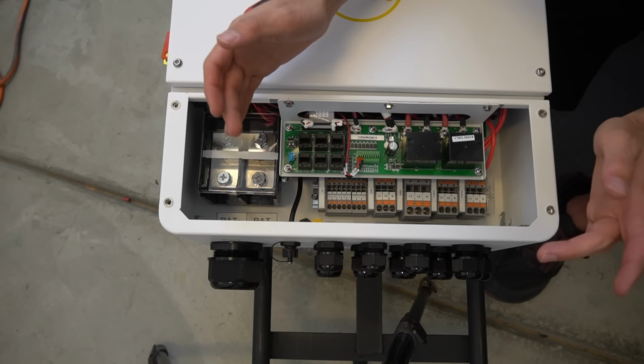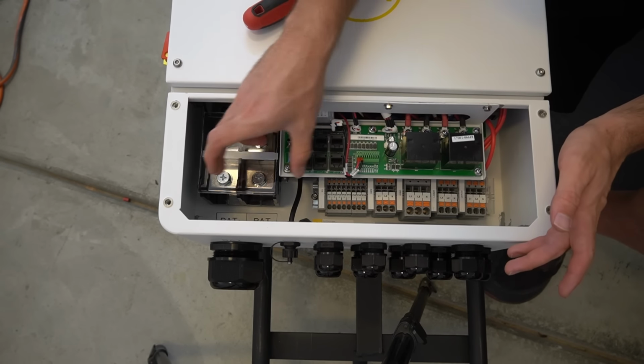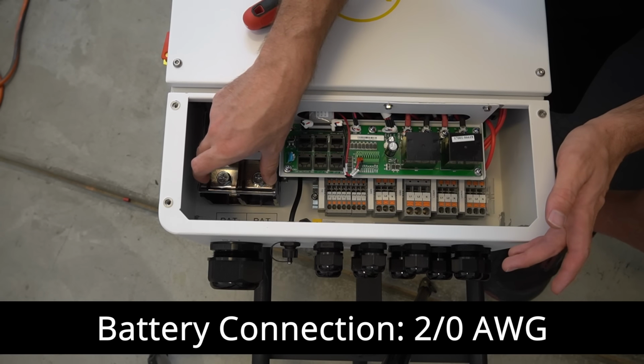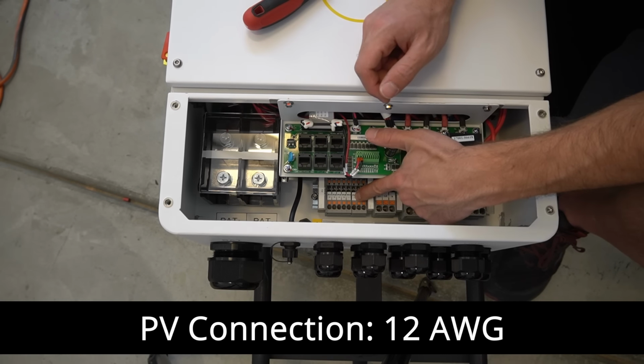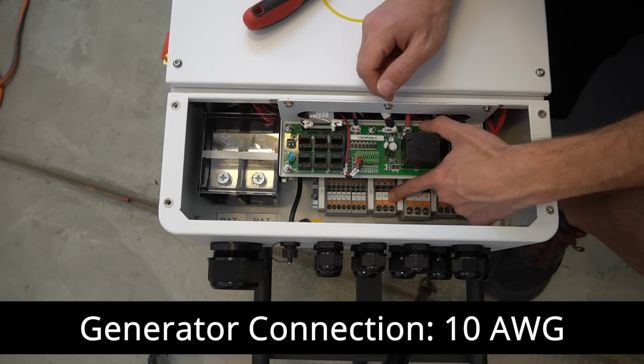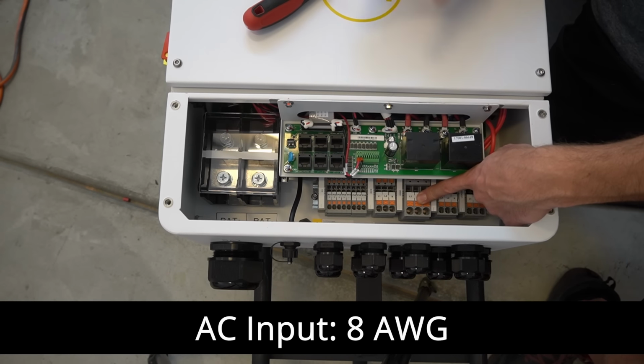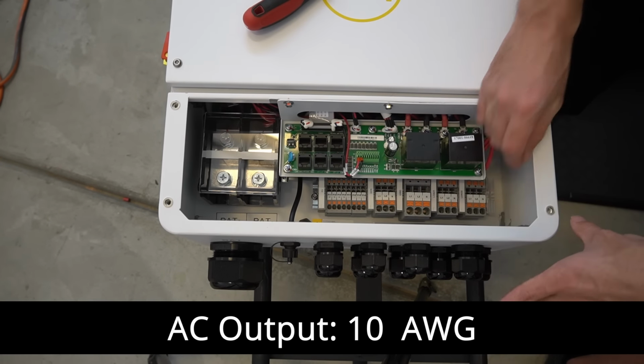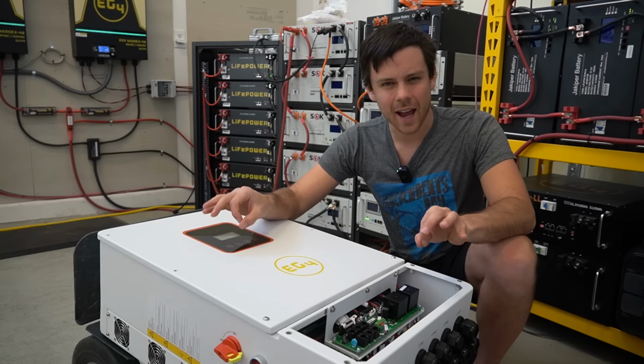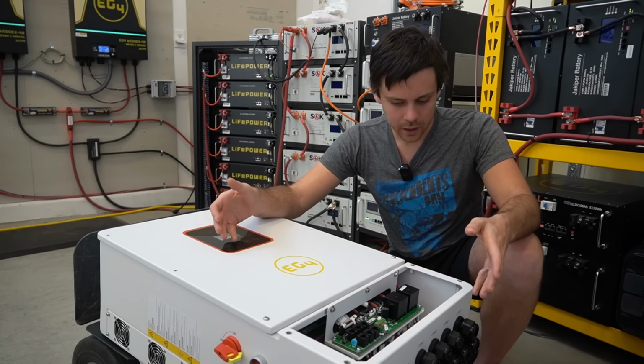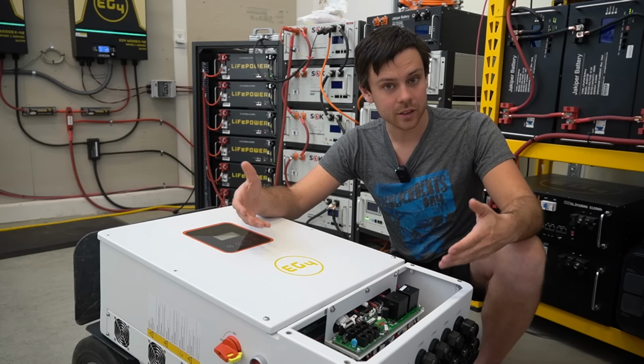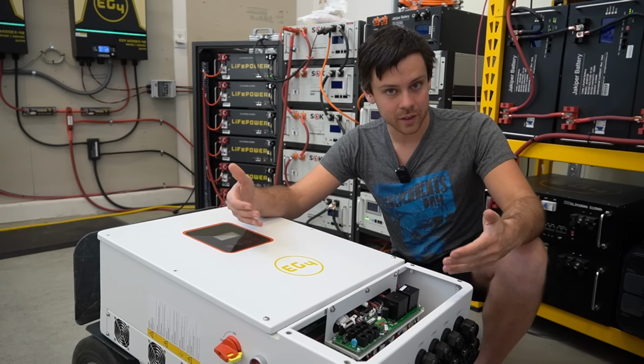Also, the manual recommends different size wires for each connection. The battery connection is 2-aught gauge. The PV connection is 12 gauge, the generator connection is 10 gauge, the grid connection is 8 gauge wire, and the AC output is 10 gauge wire. Now this model is actually grid interactive, and what that means is that you can legally, because it's certified to do so, backfeed the grid.